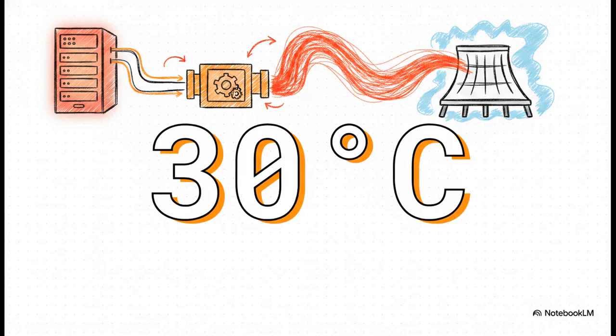If we want to dump the heat we've stripped off those servers into normal outside air, or cooling water that sits around that 30 degrees Celsius mark, a refrigerant absolutely has to be hotter than that 30-degree baseline. If it isn't, the heat's just going to stay put. So how do we force that to happen?